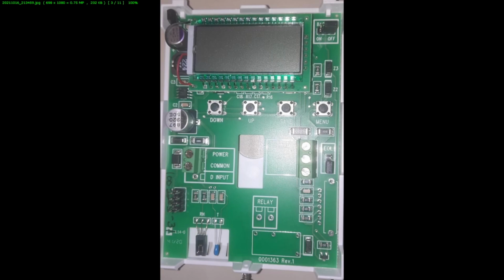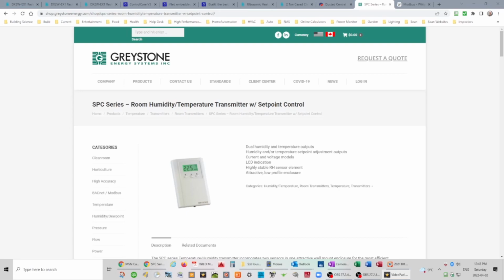So on each floor, about a foot off the ceiling in a centralized area, I have one of the sensors that provide the current humidity and temperature of that room or area. And then this is used in the code to calculate the dew points, and I'll explain why that's important in a bit. These are from Greystone, and they allow for communication via Modbus.